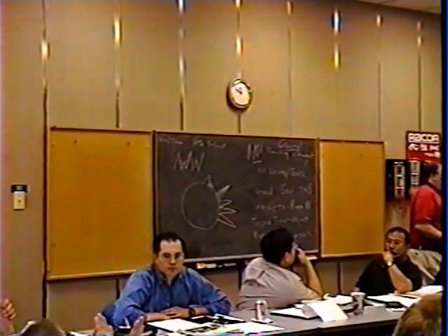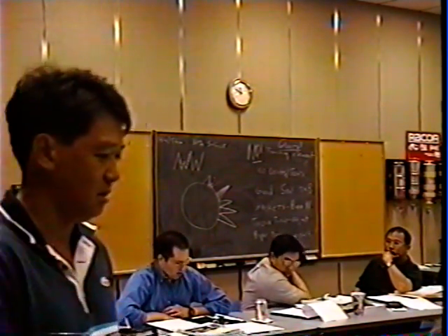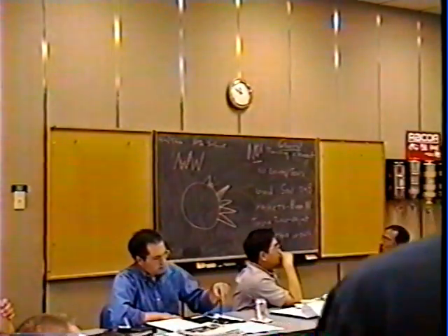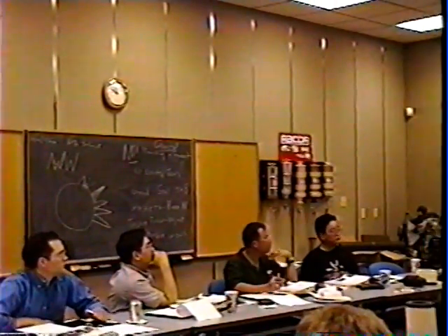So you're going to keep it overlap all the time. You're going to open up the element where you're going to use all the paper, not part of it. And when we ran a test the other day, a qualification test, when we cut the element apart, you could see down inside of the elements were white, meaning red iron oxide had not gotten down inside the pleats.